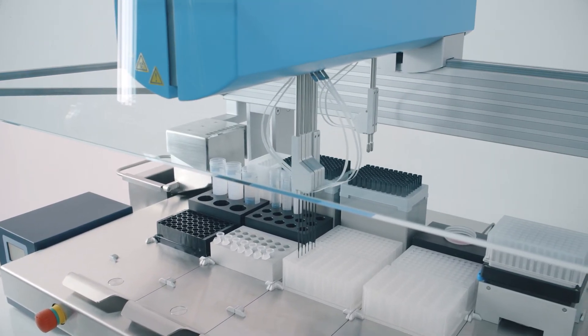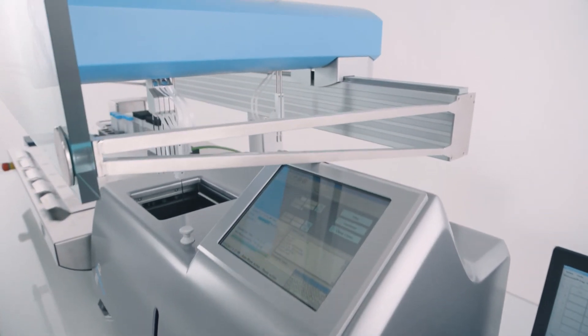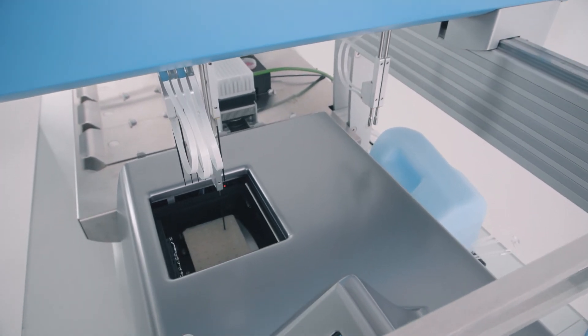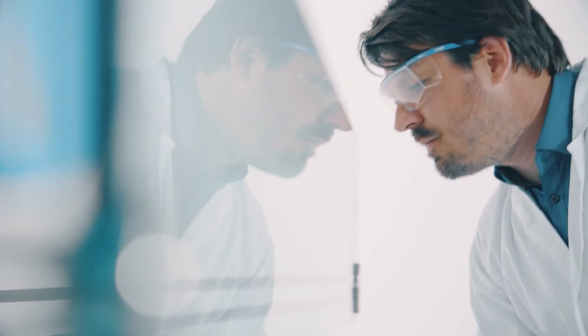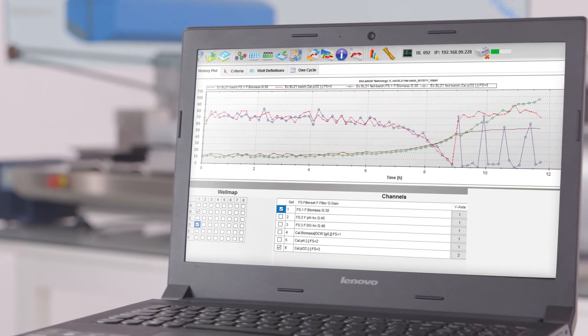The Robolector allows full bioprocess control through the addition of solutions such as inductors, acids, bases, and feed solutions into the Biolector MTP. pH adjustment and fed-batch triggers can be elicited by predefined time schedules or online process signals.